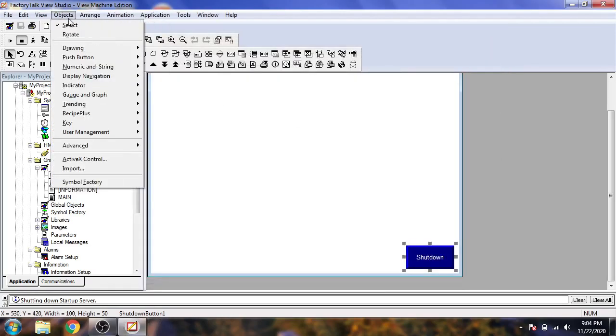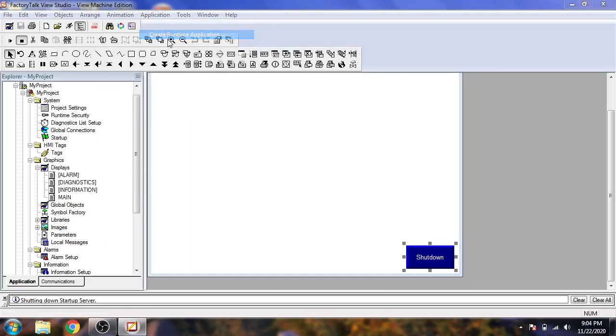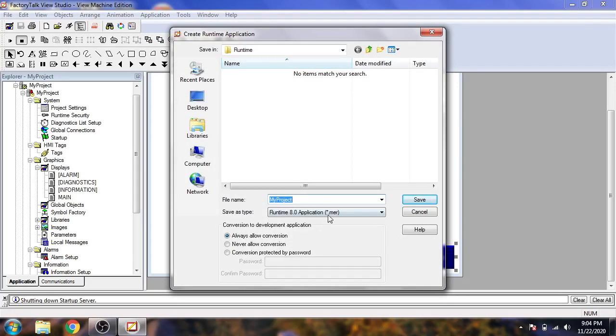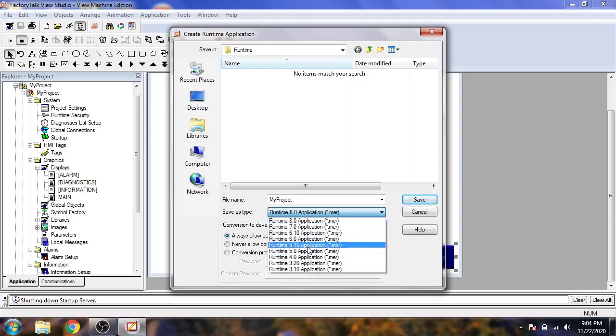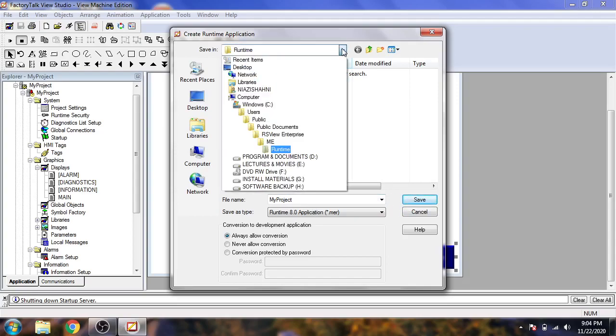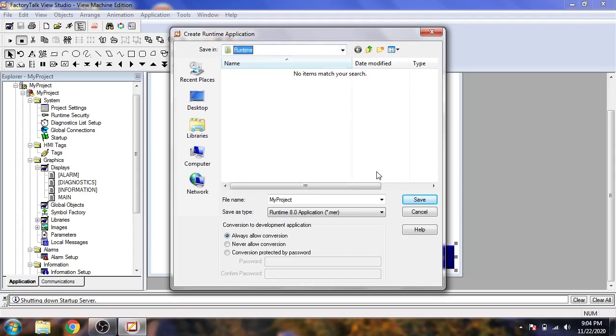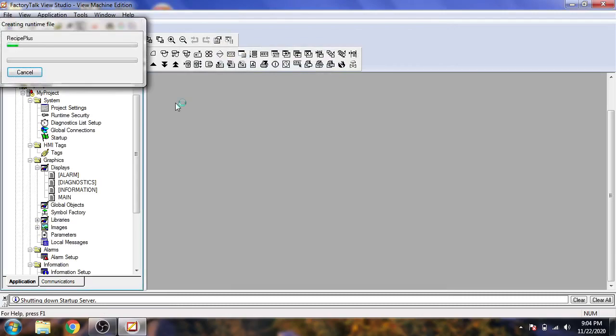Go to Application, then Create Runtime Application, and select which HMI will support that runtime. Select version 8.0 — I don't need the other version. You will see the runtime file named with the .mer extension. Save it and the runtime application will now be saved.